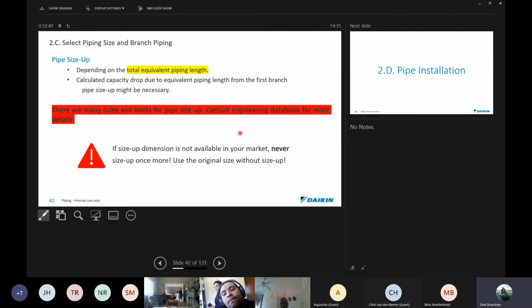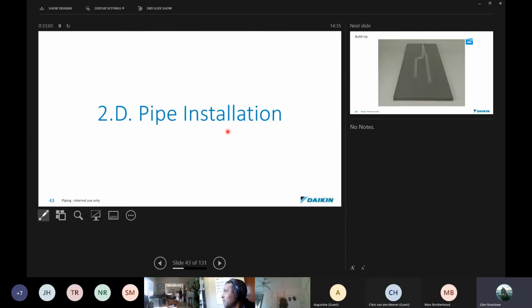Okay, and what this actually means is you'll see sometimes on some of the programs, they'll kick out a 1-inch size piping, and we don't do 1 inch in South Africa. We've got an 1 1/8 inch, and the next pipe on the other side is 7/8. If it's sized up from 7/8 to 1 inch, you don't go to 1 1/8. You just keep the piping sized at 7/8. Okay. All right, so on the piping, that was the limitations.